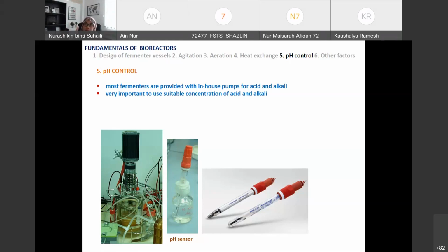Let's say we set the pH at, for example, 7. But sometimes, because so many organic products are produced inside the culture, it tends to be acidic. So when the pH probe detects that the pH inside is acidic, it will give the information to the control unit, and it will give the instruction to control the pH. How the control takes place is based on the addition of acid or alkali. So if the pH inside is acidic, let's say it is 3 or 4, but you want it to be 7, then by logic it has to be added with some alkali in order to go back from 3 or 4 to 7.